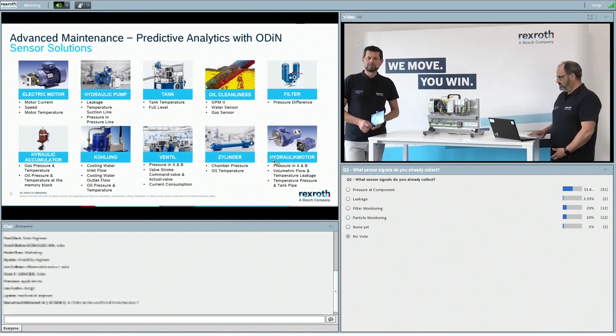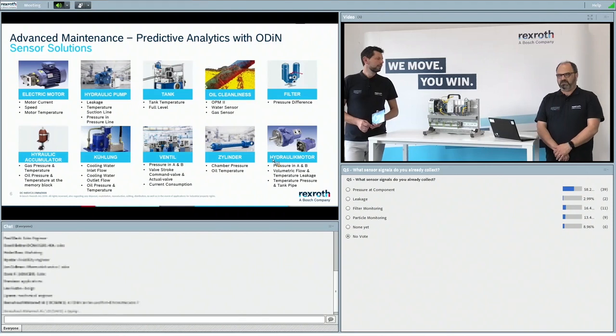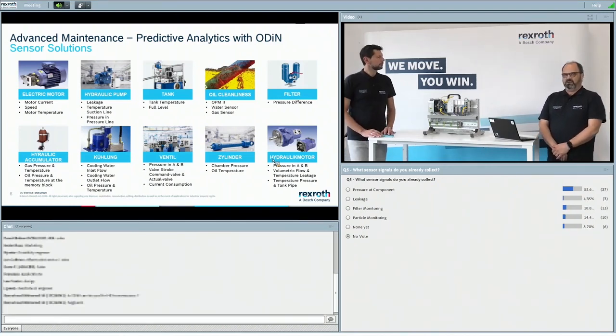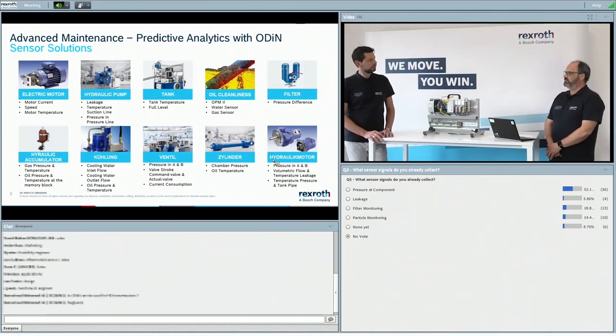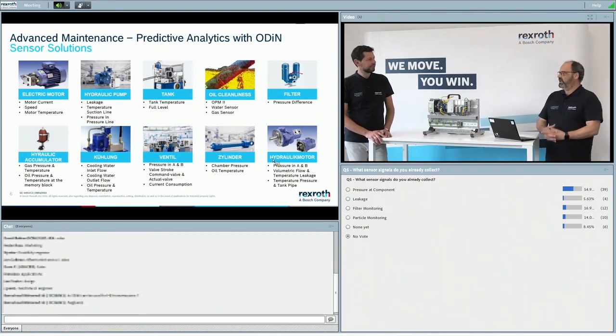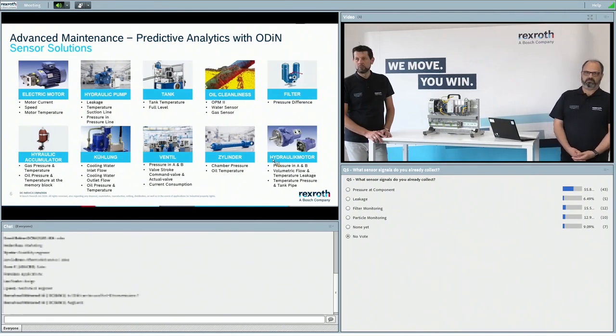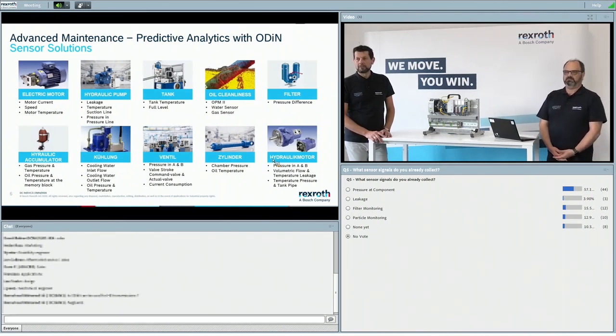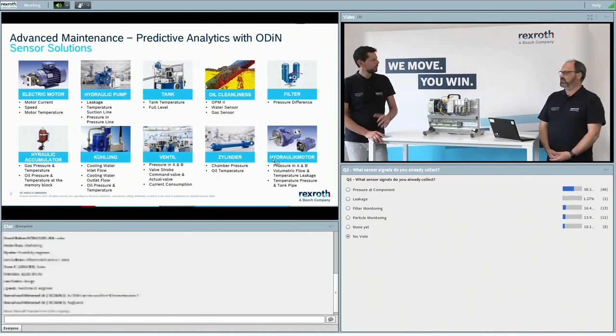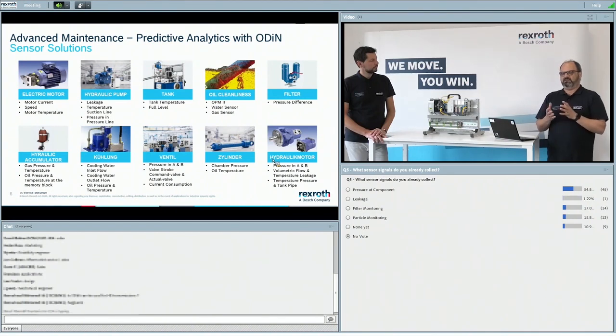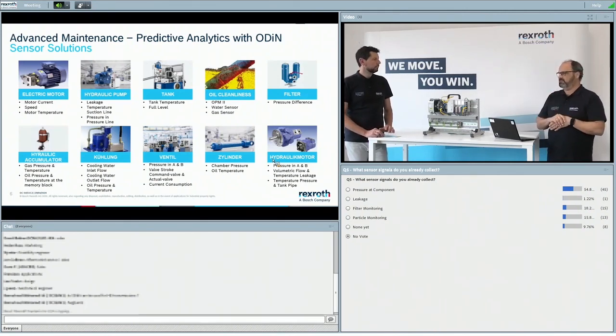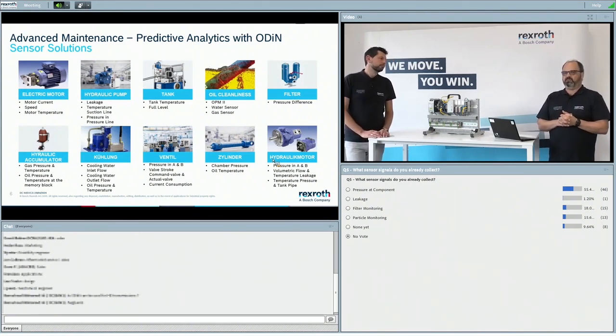One question came in: can Odin be used for Hägglunds drives? Yes — Hägglunds drives was actually one of our pilot projects four to five years ago; we have many HD systems connected. Looking at the poll results: mostly pressure sensors, followed by oil quality, filter, and particle monitoring. That's a typical picture we often find on older systems — pressure sensors around the motors or around the hydraulic pump in the HPU.